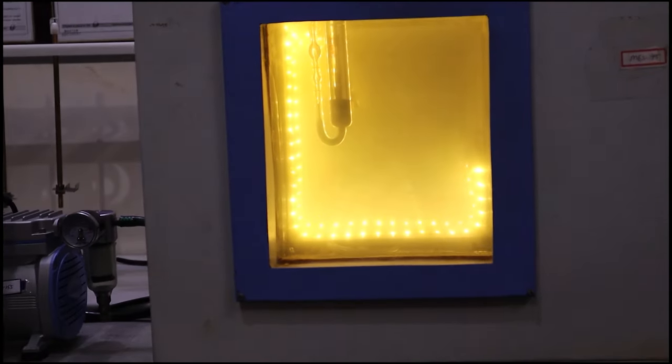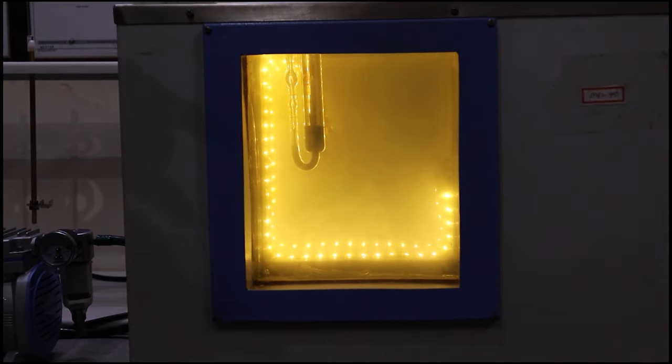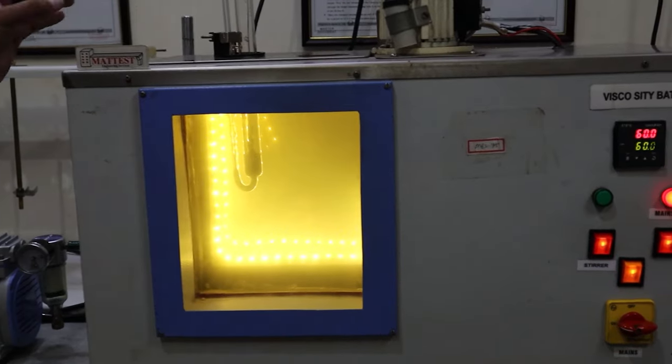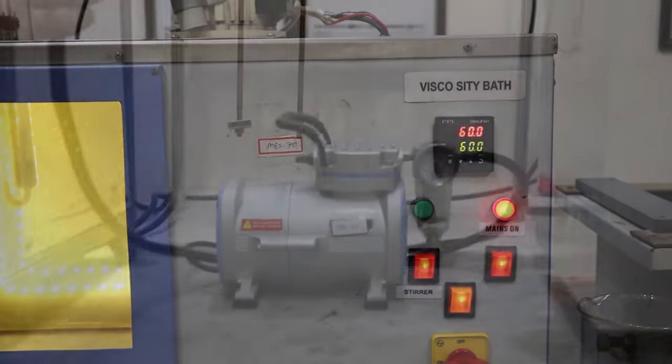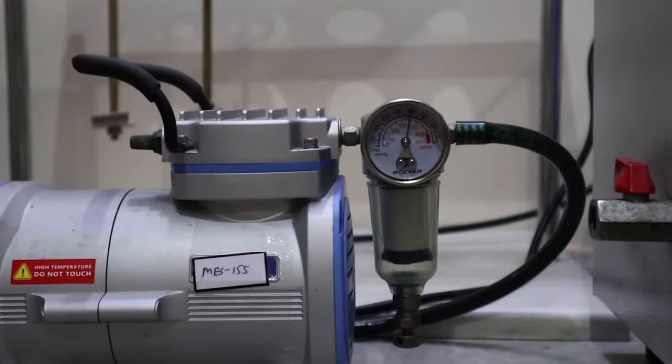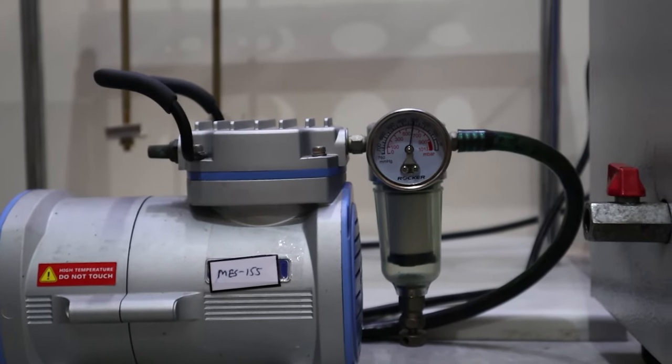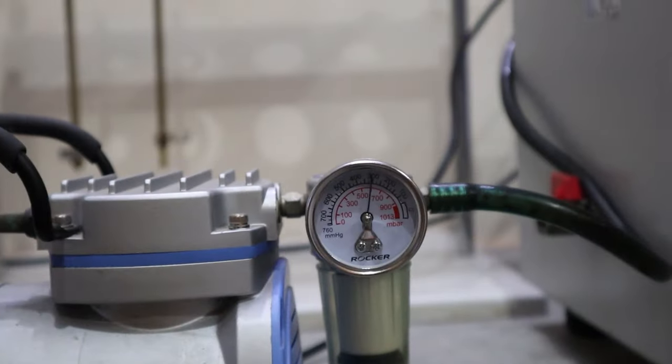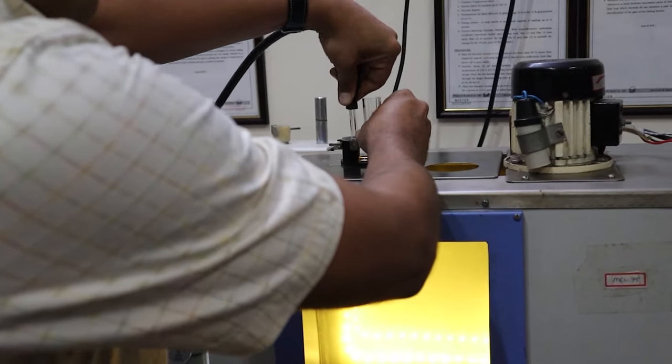After this, the viscometer is shifted to 60 degrees centigrade water bath for 30 plus or minus 5 minutes to maintain the viscometer tube temperature at 60 degrees centigrade. Establish a vacuum of 300 mm plus or minus 0.5 mm mercury in the vacuum system and connect it to the viscometer tube.